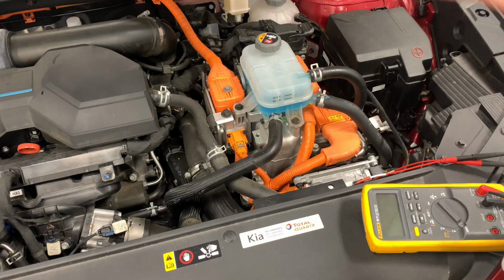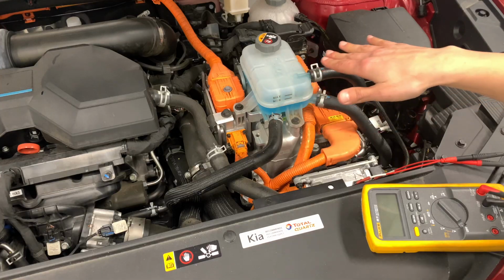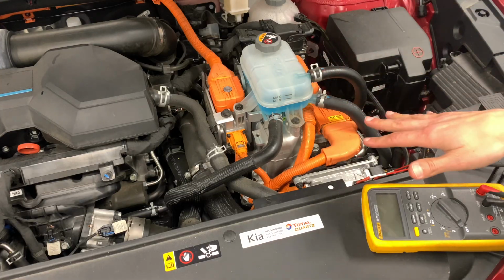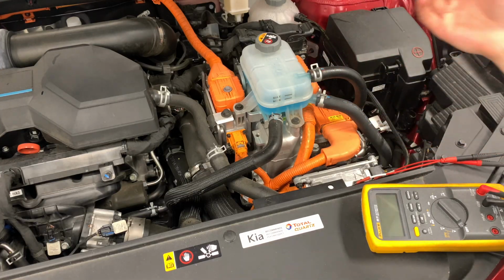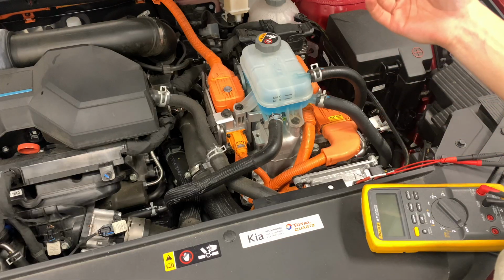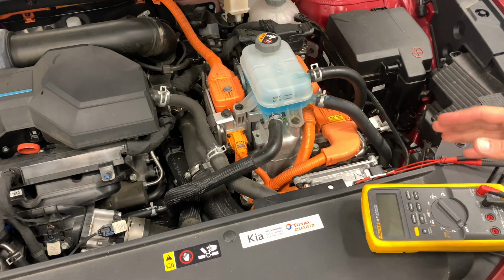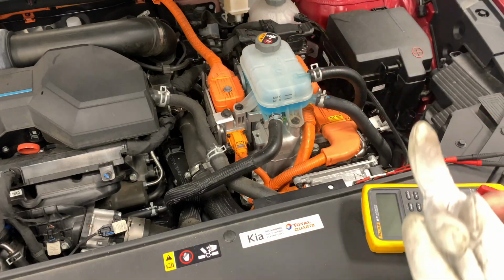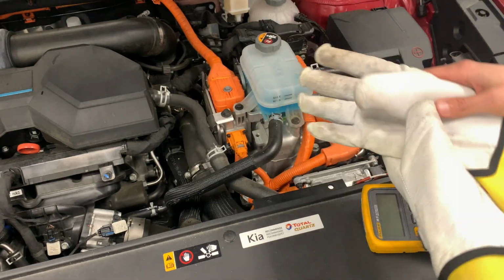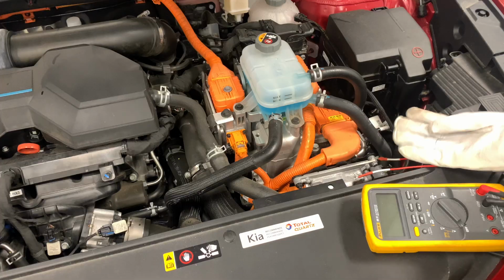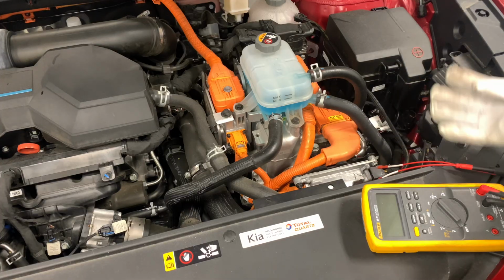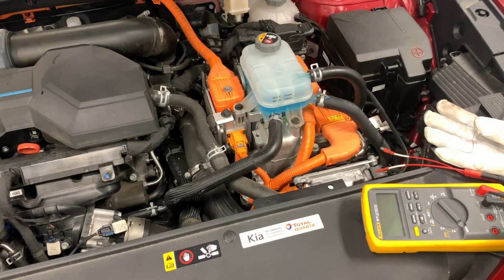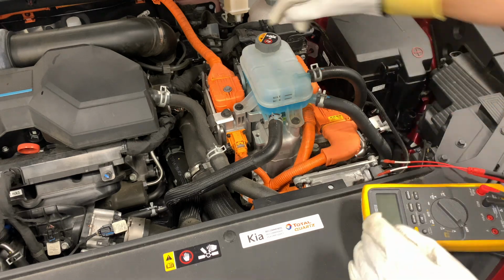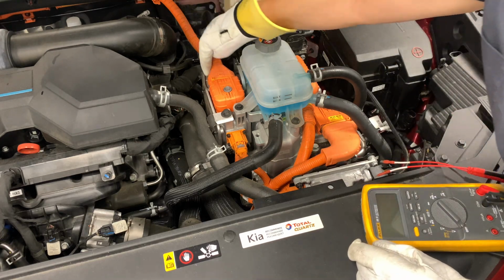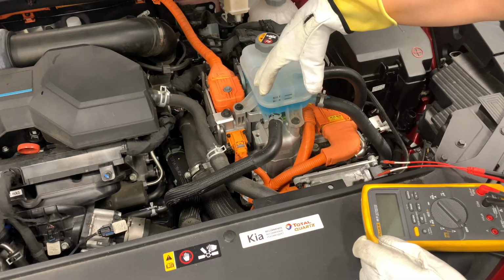At this point, the high voltage should be disconnected and disabled, but there's no real way to know for sure unless we actually test it. So this is the point where we're going to touch some orange wires, in which case I'm going to wear my gloves. We are going to test right at the cable that's coming from the battery to our inverter assembly here.